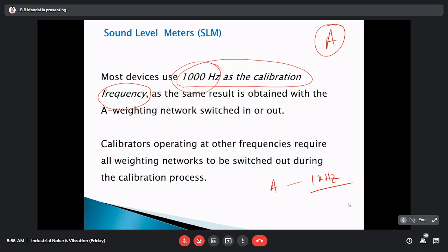And definitely when you are using an array of microphones, like 10 sound level meters all over, in a large scale survey, to compare the values from all those 10 sound level meters, you must ensure that the sound level meters are equally sensitive. That means if brought near the same source of noise, they should display the result equally. Their values should be the same all over.